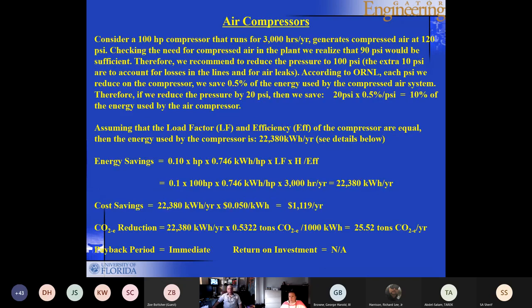Let's go to the next one, which is air compressors. If you consider, again, as an example, a 100 horsepower compressor, let us say that it's running 3,000 hours per year. It's generating compressed air at 120 psi, that's pounds per square inch. Now we go there and we realize that these guys don't really need 120 psi. They need 90 psi. They are overworking their compressors without really having a legitimate need.